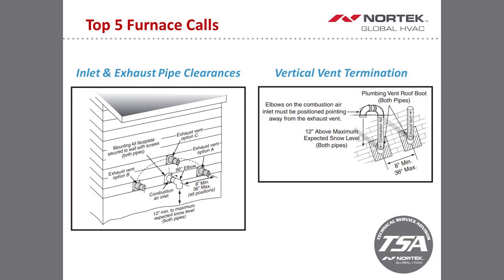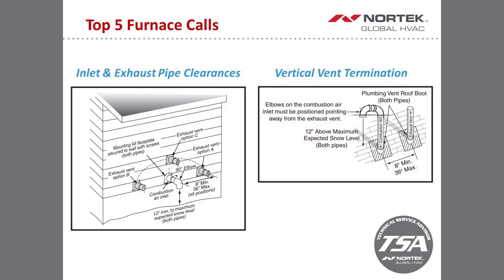What I'll also say is you want to make sure that the piping goes out the same side of the building and within those dimensions, because what you don't want to do is have the intake pipe be on one side of the building and your flue pipe be on the other side. I personally have had that call a few times through troubleshooting where I've had some really weird pressure switch calls, and that's when guys call us. It's related to pressure switch troubleshooting. But you want to make sure that the intake and the exhaust are in the same atmospheric zone, or you will have pressure switch problems. And that's your range, 8 to 36 inches on your allowable length for your intake and your flue pipe.